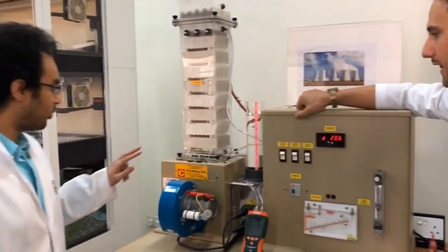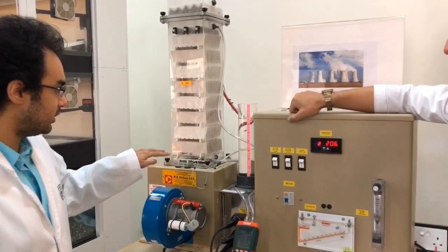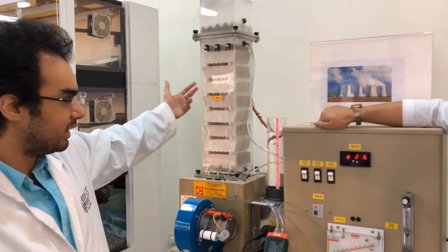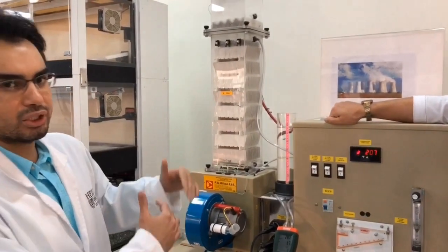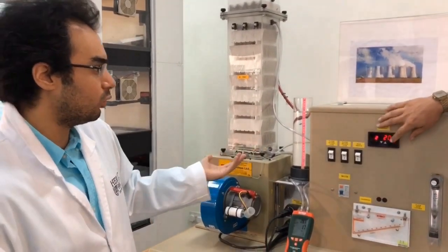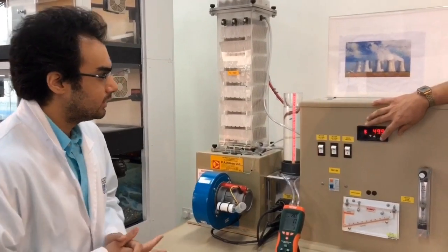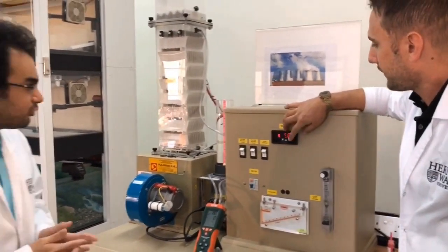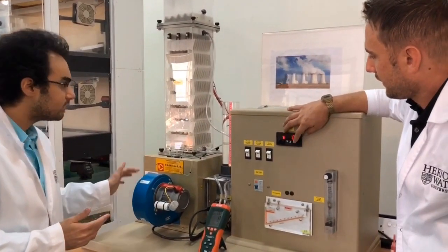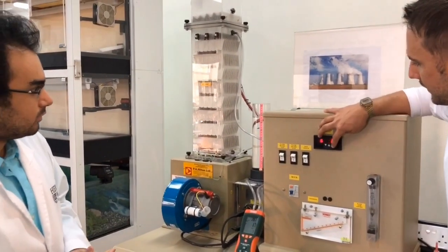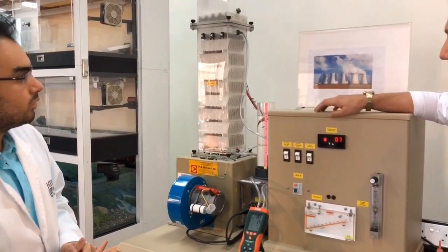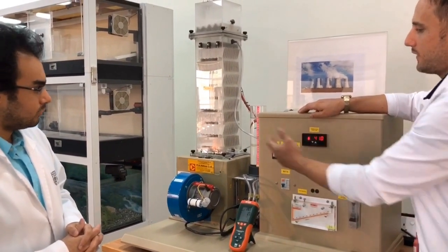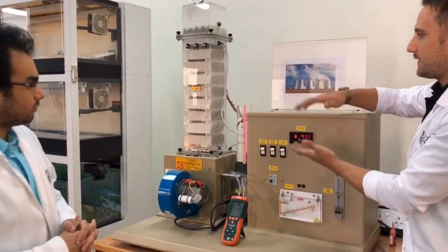Right, so we have got two thermocouples at the hot water inlet. We've got a few thermocouples at the cold water inlet, and we can now see the temperature between the hot water and the cold water. Yeah. So number 5, that's the hot water going in, almost at 50 degrees. And then number 6, it's got down to 10 degrees by the time it's got to the bottom. And we can adjust the flow rate of the water and the flow rate of the air to see the comparisons between the two.